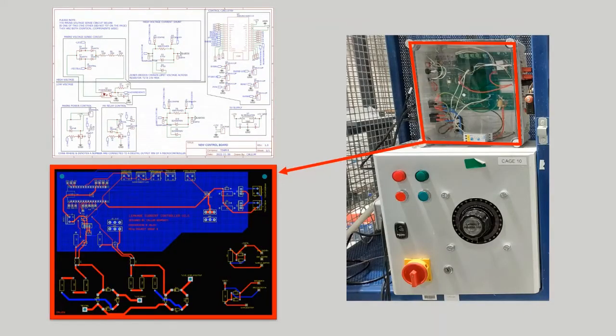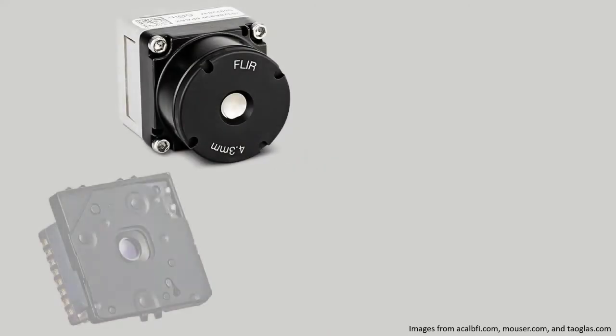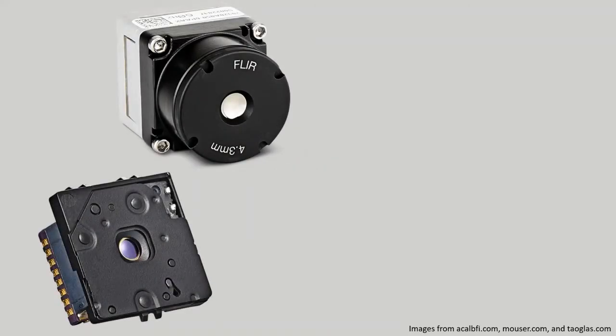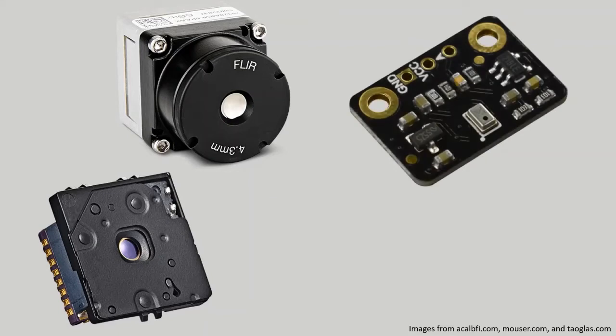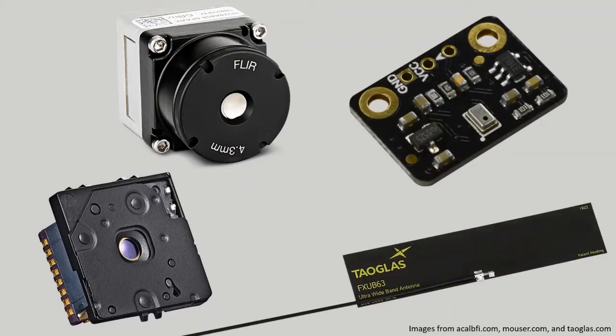The second piece of equipment created was a control box, used to monitor leakage current, which triggers a relay to disconnect mains when 20 mA is measured. This box also provides a smoke detector system and various power sources for additional equipment. To aid in the investigation of insulator aging, the following sensors were introduced. These included 2 infrared cameras, a FLIR Boson and Lepton, to provide live thermal imaging of the tests, a microphone module to monitor auditory activity, and an ultra-high frequency antenna to provide insight into the frequency of discharges.